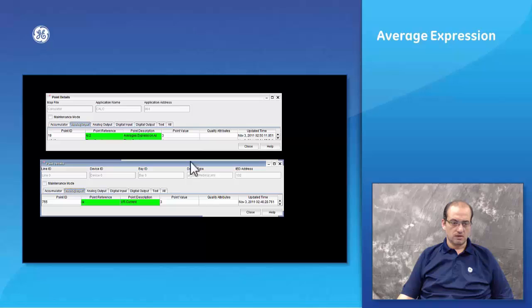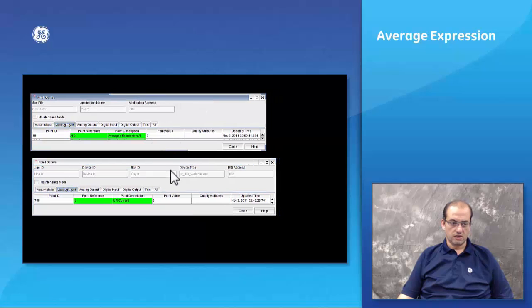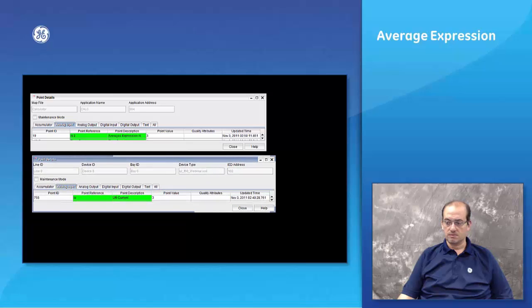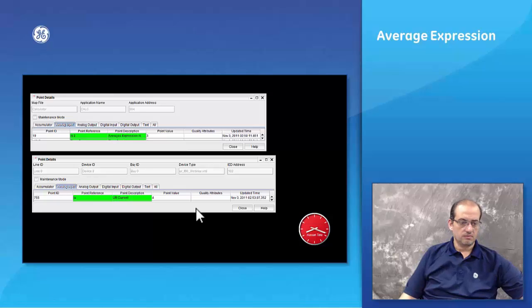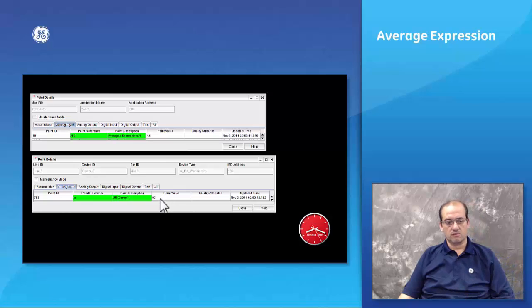Set it up. So the current is reading 3. As such, the average at this point is 3, right? And then every 25 seconds, that average will be updated. So I'm going to vary it. As you can see, we're reading 92 from the device in the field, and the average started to go up as expected. I'm just going to keep it at 92, and the average should increase even more in the next minute.